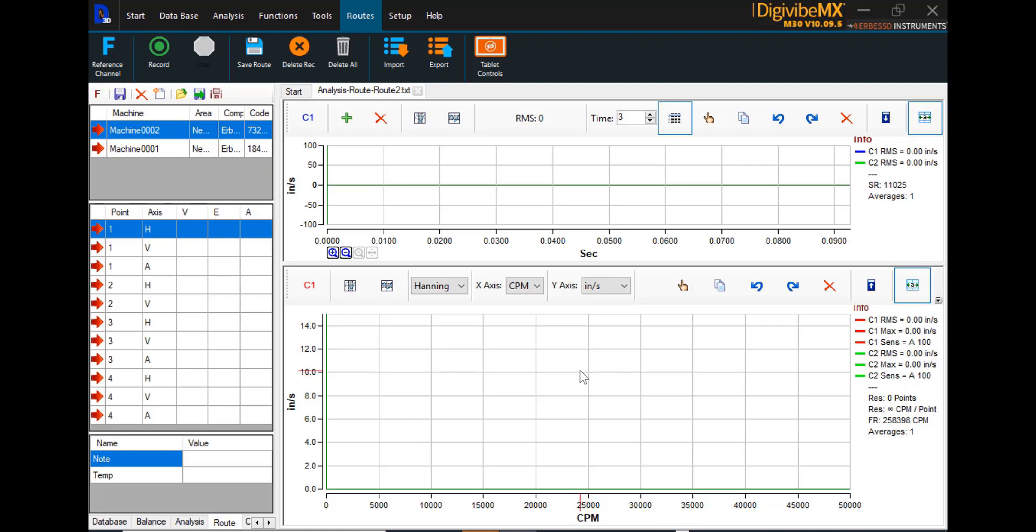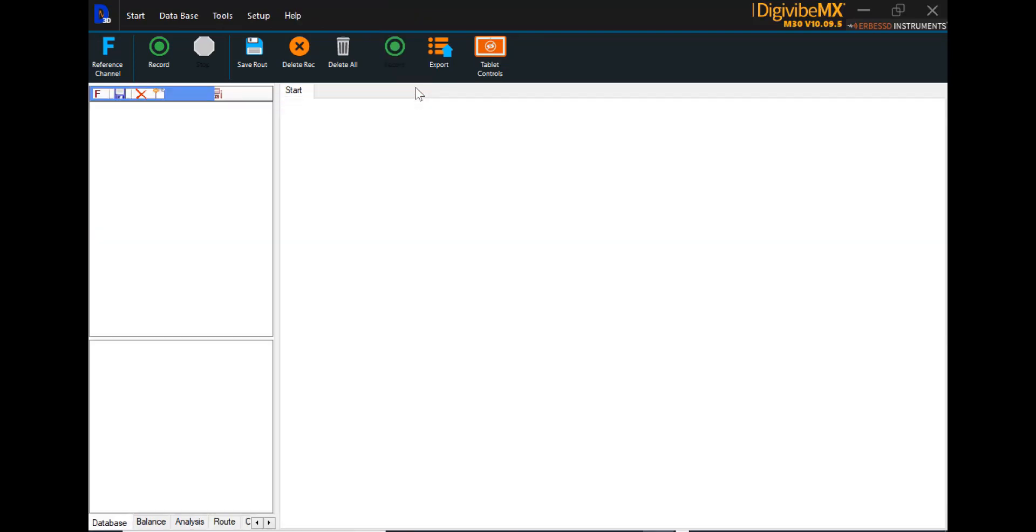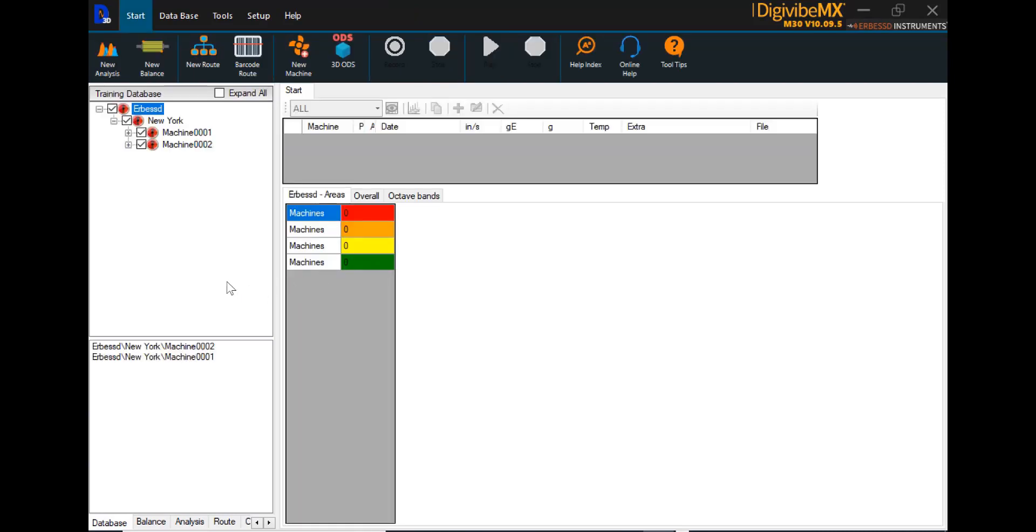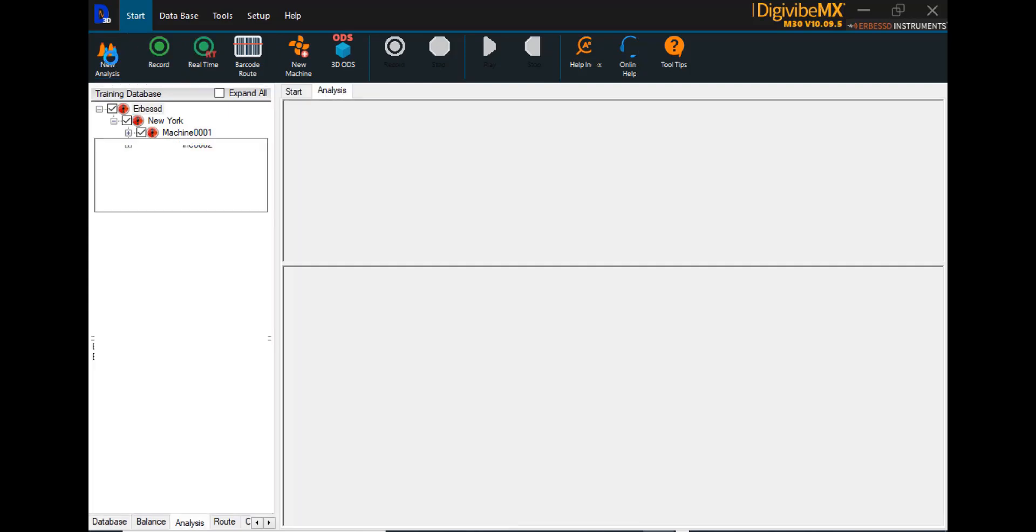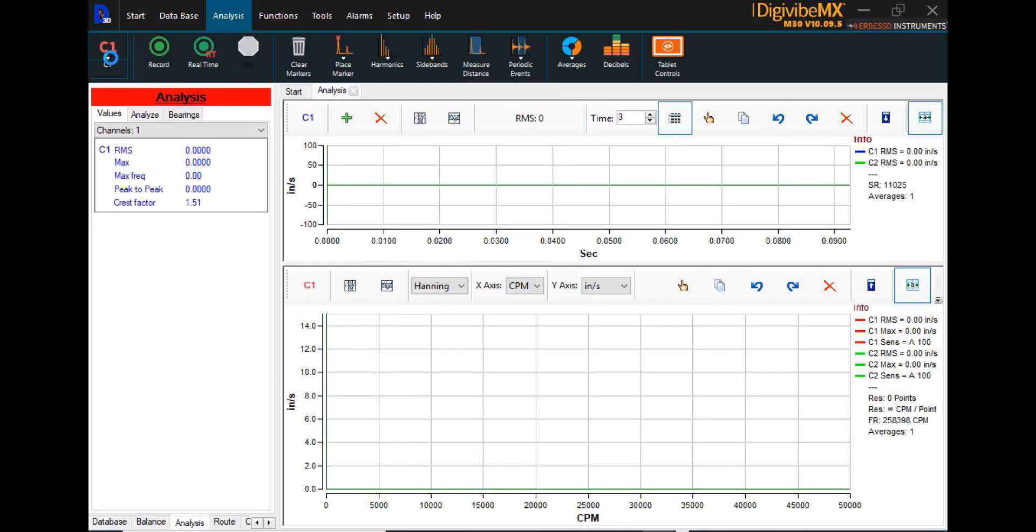Collecting data in DigiVibe MX does not necessarily require route data collection. There are other ways to go collect data or what we may call off-route data as needed. So let's close this route analysis tab again. Back at the start menu, in the list of options on the left-hand side is new analysis. You can initiate a new analysis immediately at any time. Simply select new analysis. Place the accelerometer on the point that needs to be collected. Time is currently set for three seconds by default. You can increase that time if you need to.